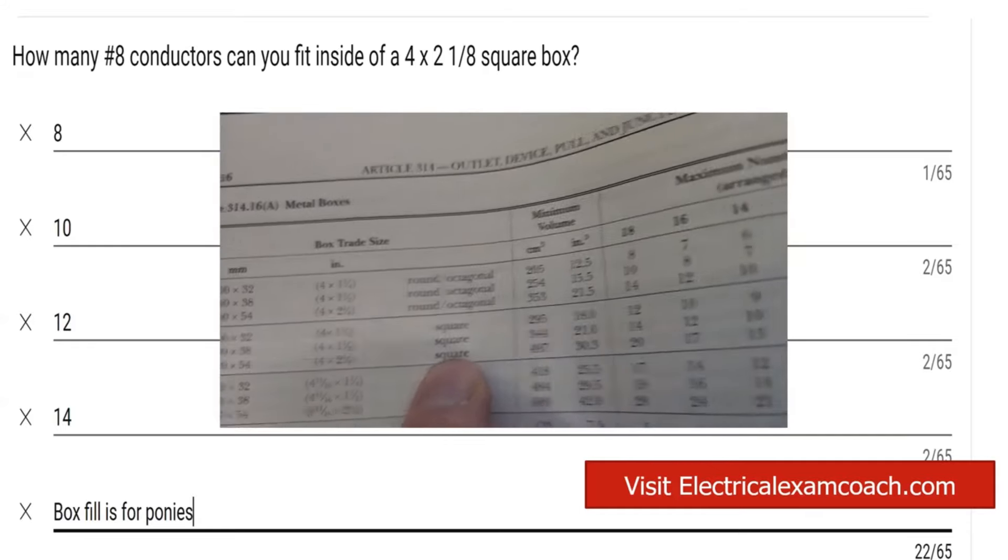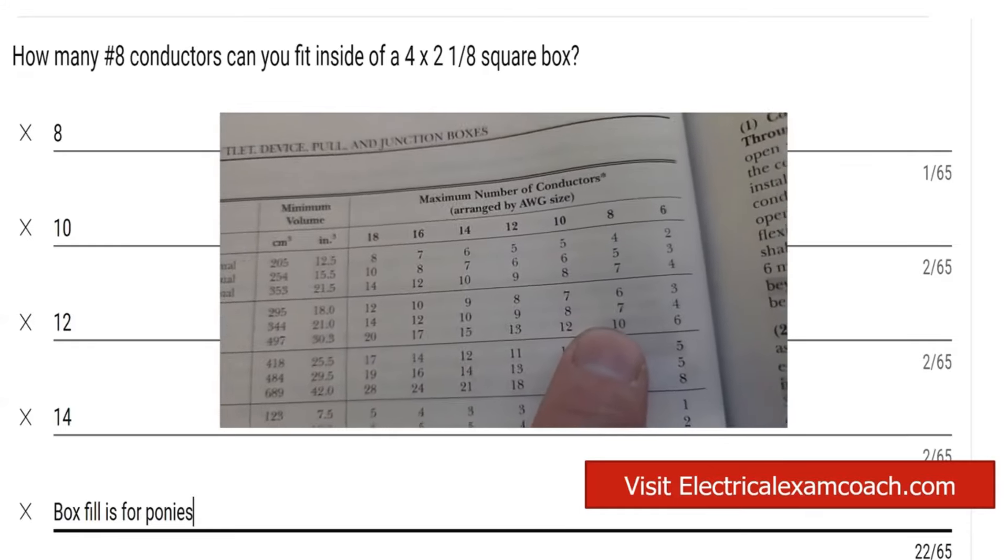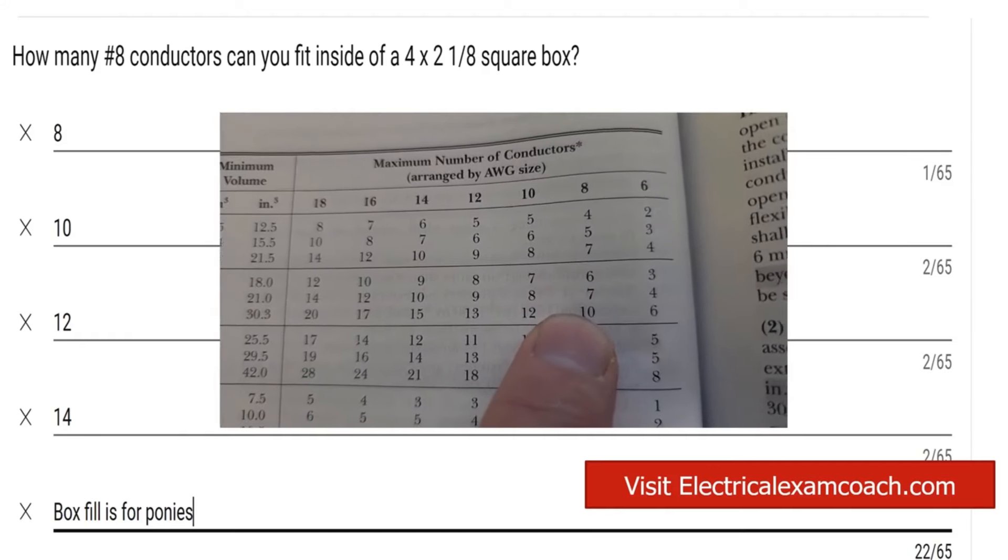We're going to come over here to the four square boxes. We're going to slide over to number eight conductor, and we're going to find that you're allowed to fit 10 number eights.